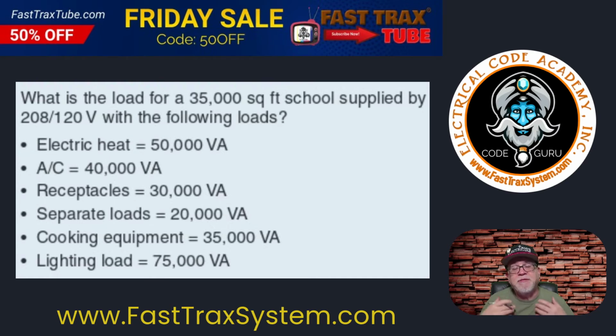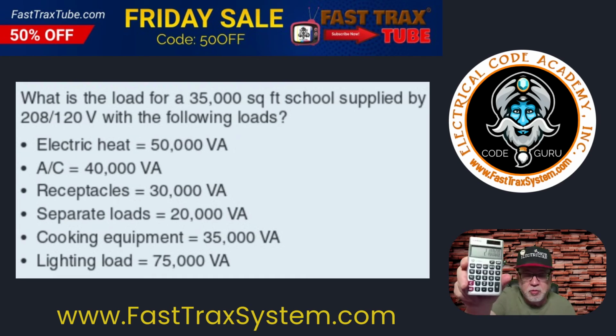Now, how do we find out what it is per square foot? Well, you take that 210,000 and you divide it by the 35,000, which is the square footage, and that gives me 6 VA per square foot. So 6 VA per square foot, and you can verify this by just taking the 35,000 times 6, and that equals 210,000.